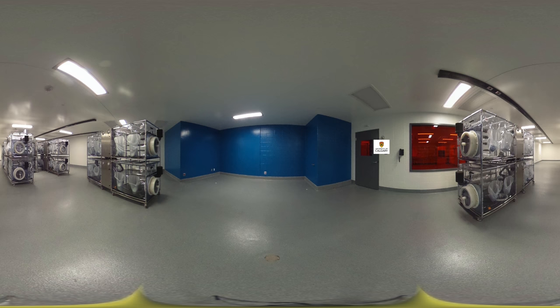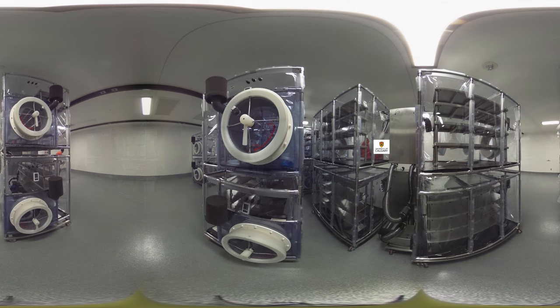This room we're in right now is at positive pressure — 50 pascals. Our first room here is called the axenic breeding room. Exenic is just another word for germ-free, and this room is our highest pressure and our cleanest area. It's at plus 75 pascals and will hold the isolators that house the germ-free animals.